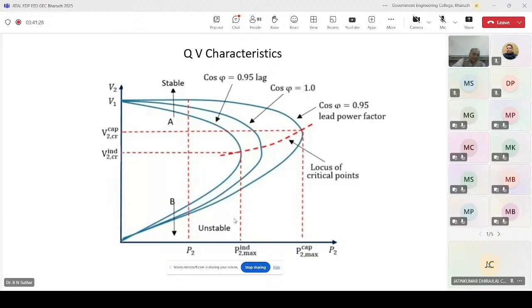So what does it indicate? Whenever you have a very good power factor, leading power factor or unity power factor, your PV or QV curve becomes flat. That means when the curve is flat, you have variation in the x-axis, but the variation in the y-axis is very small. So what will happen if your load power factor is, let us say, lead 0.95? In that case, whether you are drawing P1 power or P2 power or P2 max, the change in the voltage is very small.